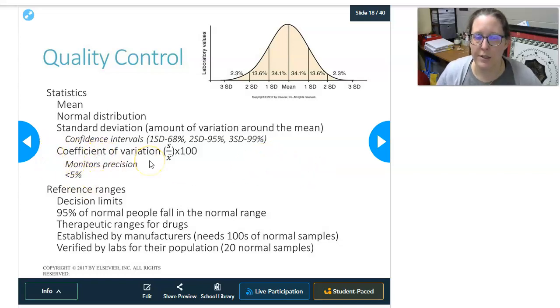It monitors precision. So the mean and the standard deviation really assess accuracy. The further away you are from the mean, the less accurate you are. The coefficient of variation will tell you how tightly around the mean these points are. It also has to do with the shape of your curve. Is your curve wide, or is your normal distribution curve really tight? Generally speaking, in the lab, for a chemistry test, you want your coefficient of variation, calculated by your analyzer, to be below 5%. If you're less than 5%, that means you have good precision for that specific analyte. If you're above 5%, then you're having some precision issues with that analyte. Ideally, less than 3% is even better, but 5% seems to be a good accepted number.